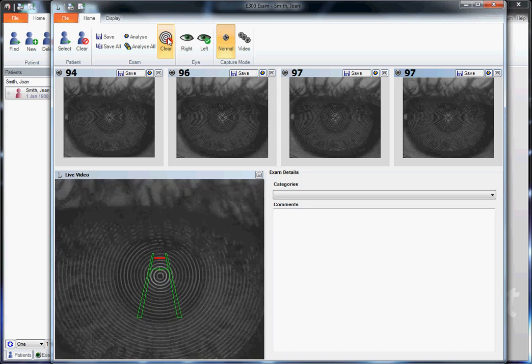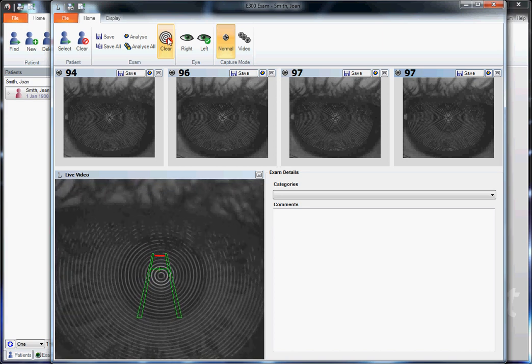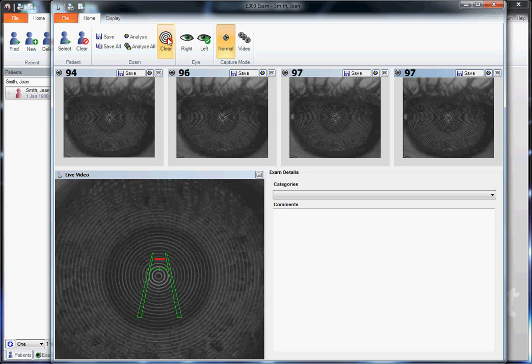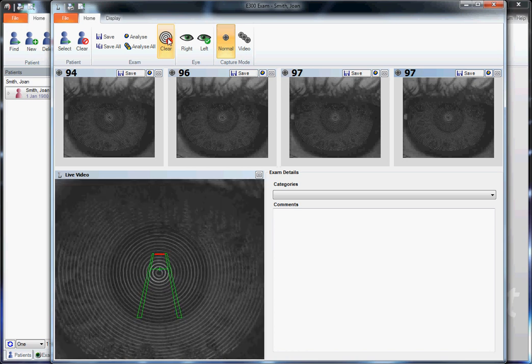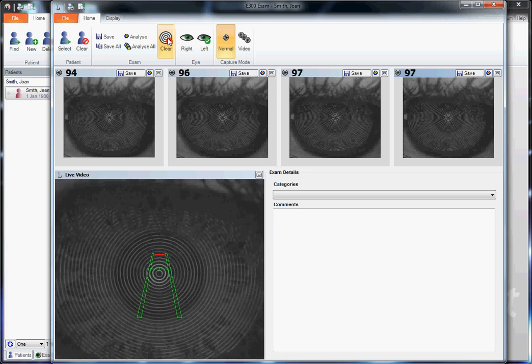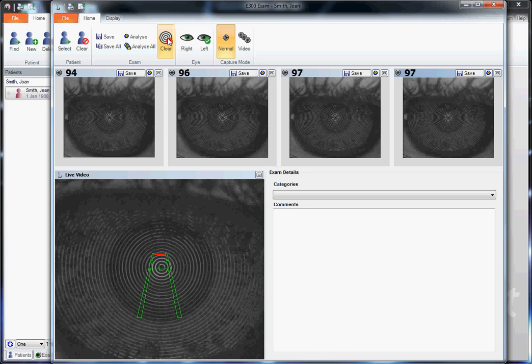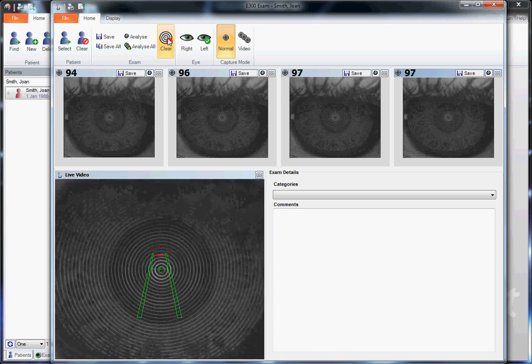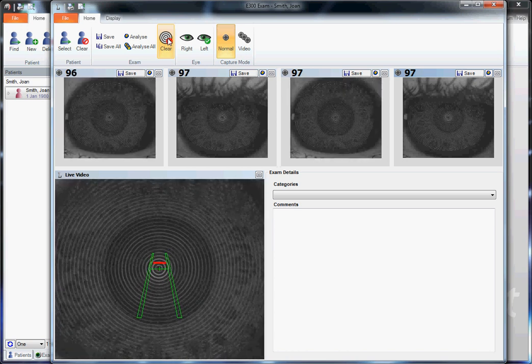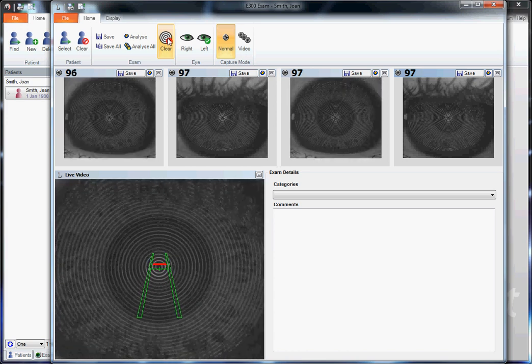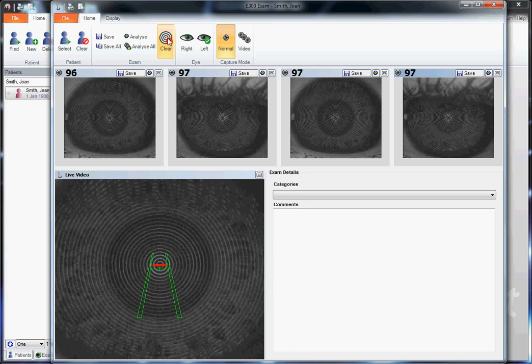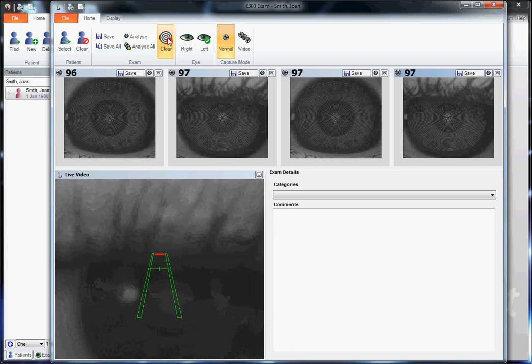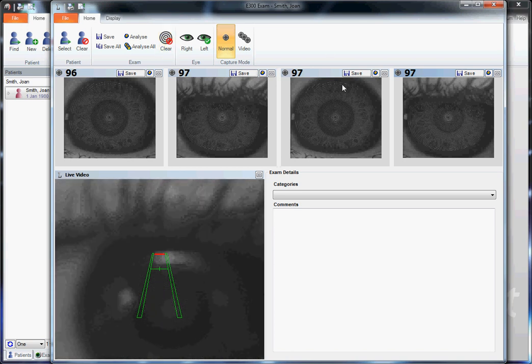Let's also consider the lid and the lashes. Let's ask our patient to open up as wide as possible. Take a blink just prior to capture, and we'll ask our patient to blink. Move the instrument into position. Try to get an image with the eyelid out of the way.